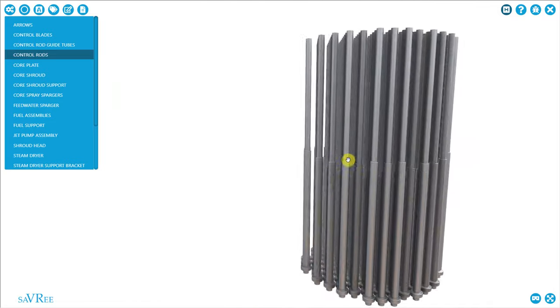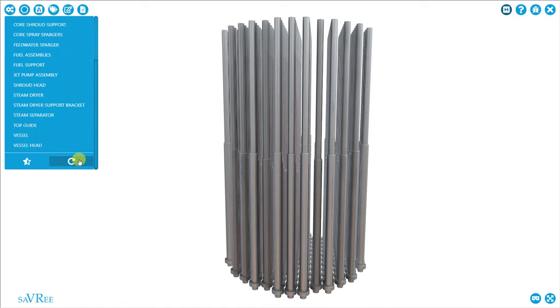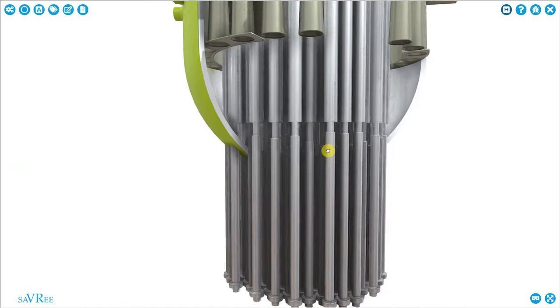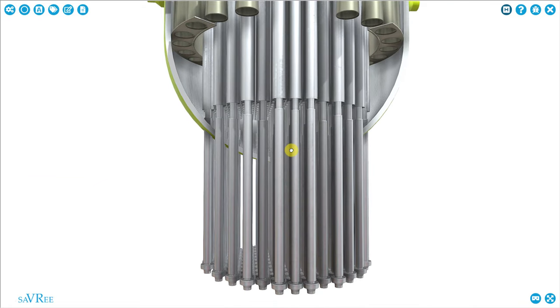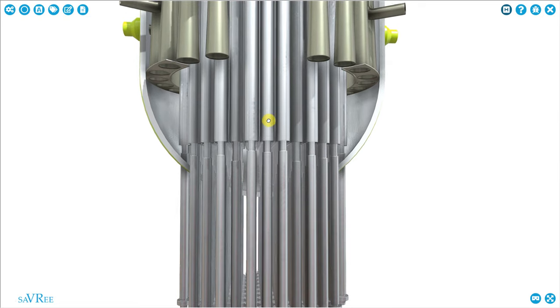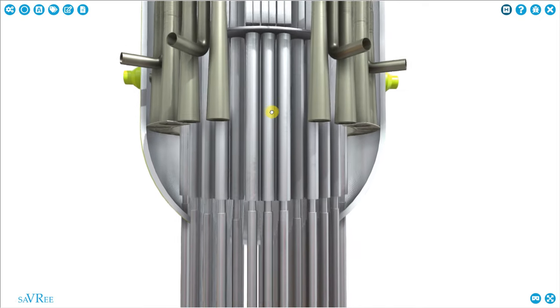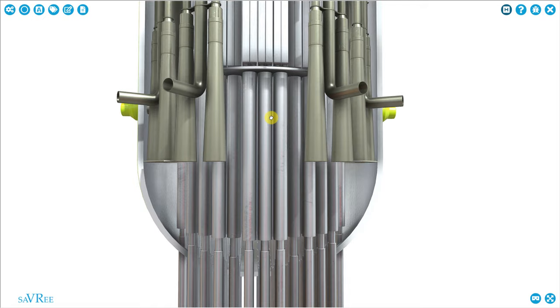Or maybe we want to install the control rods for safety reasons. For example, to stop a runaway reaction. What's unusual about the control rods is that they're fed into the BWR from the bottom, whereas almost all other reactor designs feed the control rods in from the top and they'll fall due to gravity. The ones on this design are actually fed into the BWR using a hydraulic circuit. And you can use an accumulator, which is essentially a pressure vessel, as a way in an emergency to push the control rods in even if you don't have any electrical power. For example, when you have a blackout. Safety, as always, is a very big factor in a nuclear power plant, as it should be.